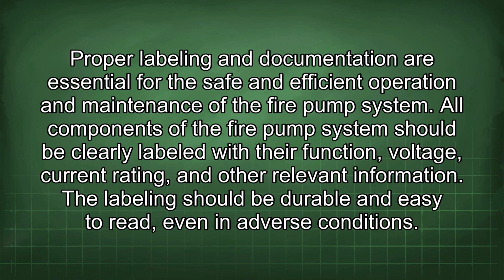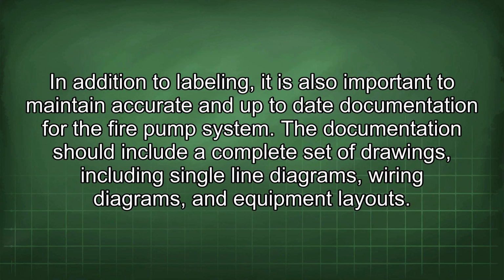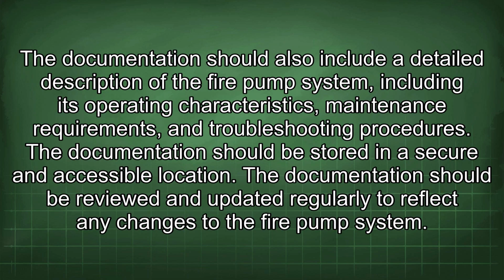Proper labeling and documentation are essential for the safe and efficient operation and maintenance of the fire pump system. All components of the fire pump system should be clearly labeled with their function, voltage, current rating, and other relevant information. The labeling should be durable and easy to read even in adverse conditions. In addition to labeling, it is also important to maintain accurate and up-to-date documentation for the fire pump system. The documentation should include a complete set of drawings, including single-line diagrams, wiring diagrams, and equipment layouts. The documentation should also include a detailed description of the fire pump system, including its operating characteristics, maintenance requirements, and troubleshooting procedures. The documentation should be stored in a secure and accessible location. The documentation should be reviewed and updated regularly to reflect any changes to the fire pump system.